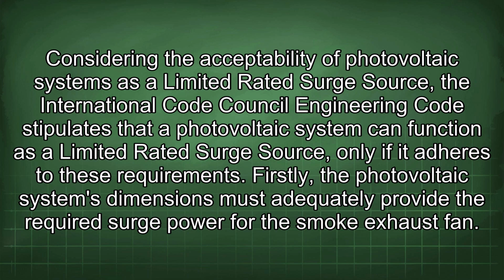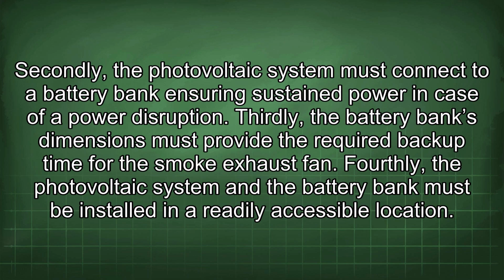Code stipulates that a photovoltaic system can function as a limited rated surge source only if it adheres to these requirements. Firstly, the photovoltaic system's dimensions must adequately provide the required surge power for the smoke exhaust fan. Secondly, the photovoltaic system must connect to a battery bank, ensuring sustained power in case of a power disruption. Thirdly, the battery bank's dimensions must provide the required backup time for the smoke exhaust fan. Fourthly, the photovoltaic system and the battery bank must be installed in a readily accessible location.